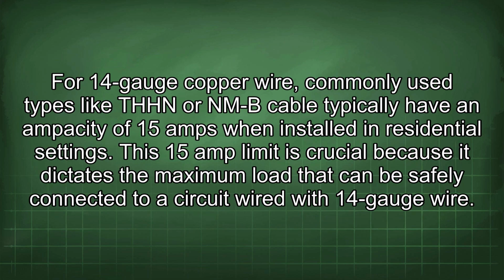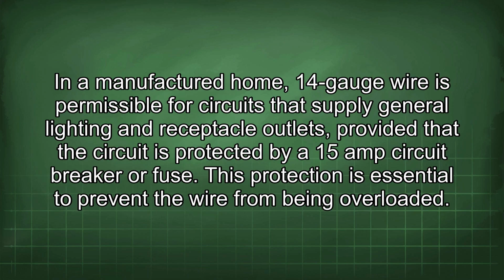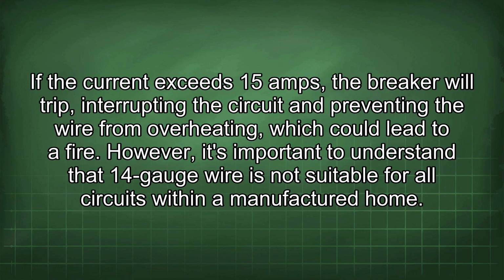For 14-gauge copper wire, commonly used types like THHN or NMB cable typically have an ampacity of 15 amps when installed in residential settings. This 15 amp limit is crucial because it dictates the maximum load that can be safely connected to a circuit wired with 14-gauge wire. In a manufactured home, 14-gauge wire is permissible for circuits that supply general lighting and receptacle outlets, provided that the circuit is protected by a 15-amp circuit breaker or fuse. This protection is essential to prevent the wire from being overloaded. If the current exceeds 15 amps, the breaker will trip, interrupting the circuit and preventing the wire from overheating, which could lead to a fire.